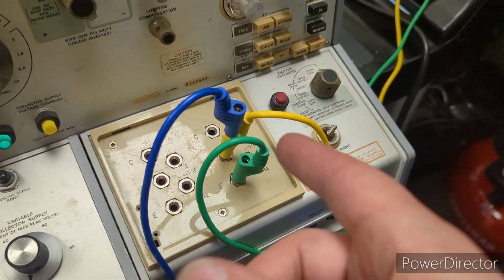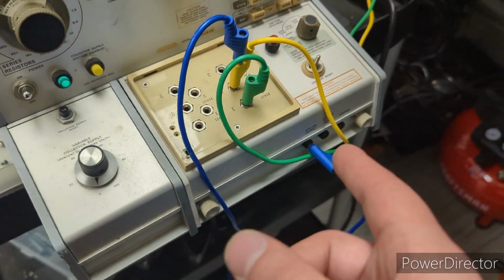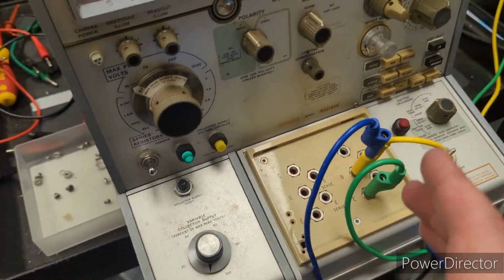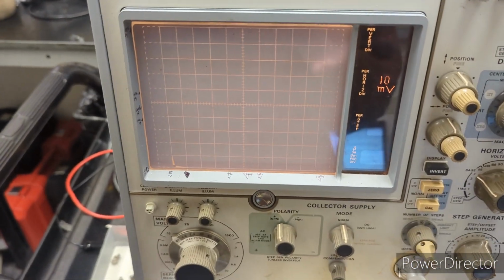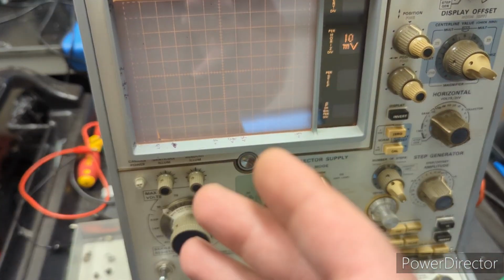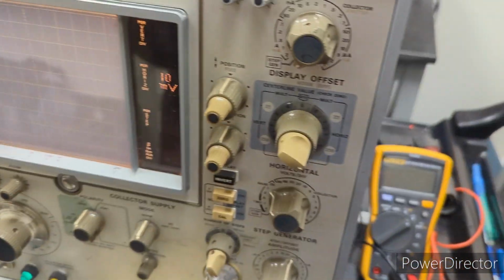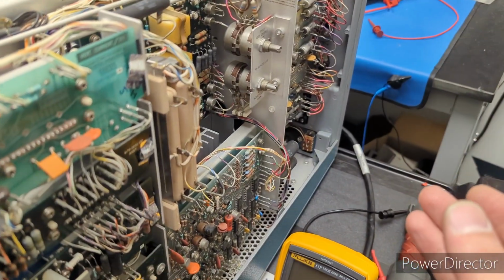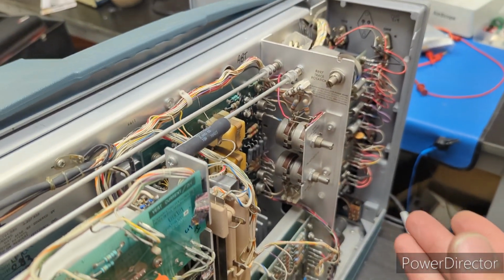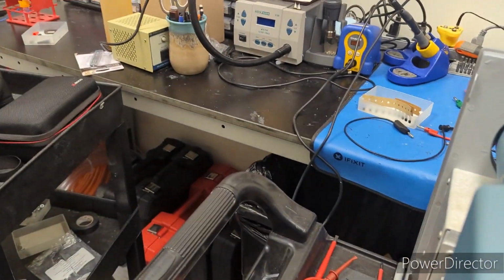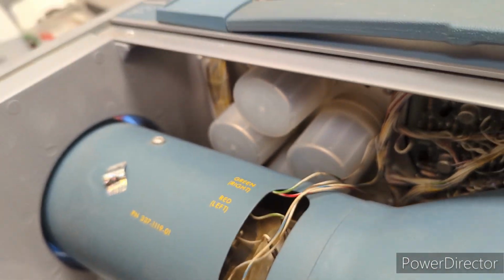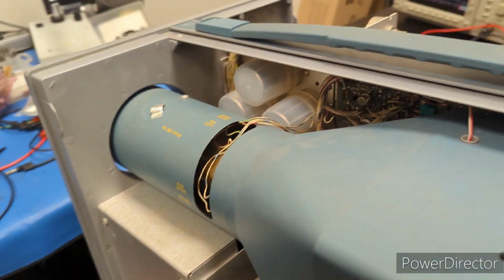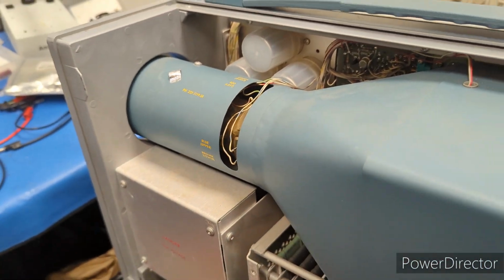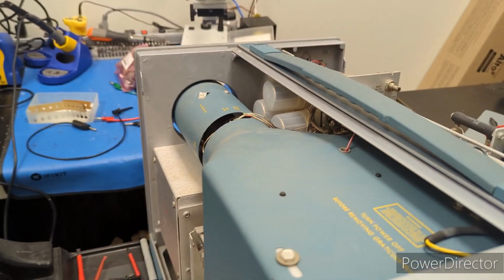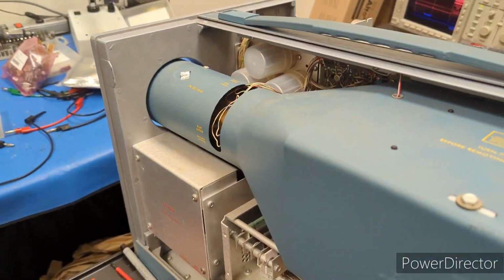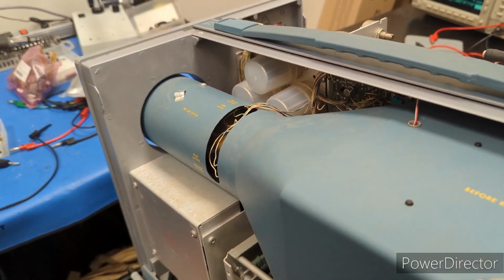There was a blown resistor on the terminal selector switch, a 22 ohm resistor, that I also replaced. And once those things were done, in my first video I wasn't able to test a transistor. So I started looking at other areas of the instrument, checked the power supply, and found that all the voltage rails were low. It turned out to be capacitor C707, which is one of these big capacitors. So I replaced that, gutted the original and put a modern one in there so I could still keep the solder lugs. Once that was fixed, all the voltages came into spec after adjusting the trimmer pot on the low voltage regulator board.